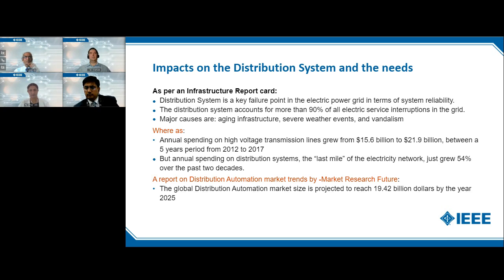What we see from this is that the distribution sector has been neglected, and we need to focus more on this. Keeping in view the impacts of the distribution system being so scattered and having a large number of aging equipment - wires, poles, transformers, breakers, all 50 to 60 years old, and widely scattered - monitoring all these things remotely and on a real-time basis is a big challenge. So what are some distribution automation technologies and products available to enhance reliability, especially for this scattered system?